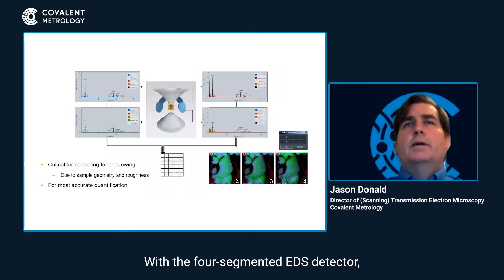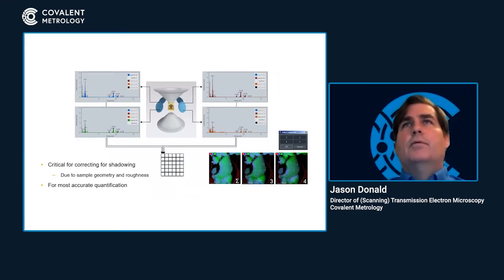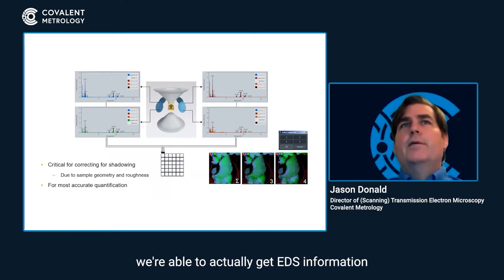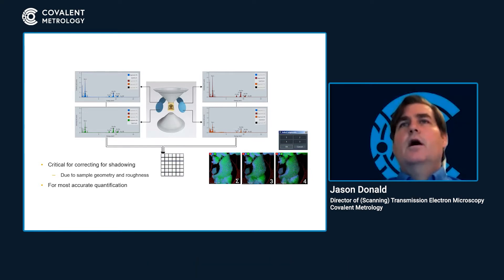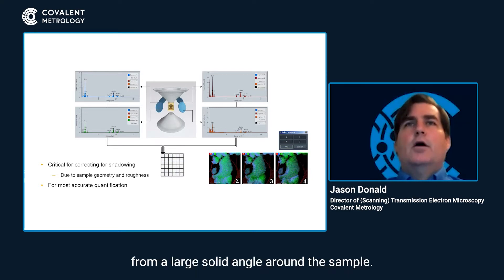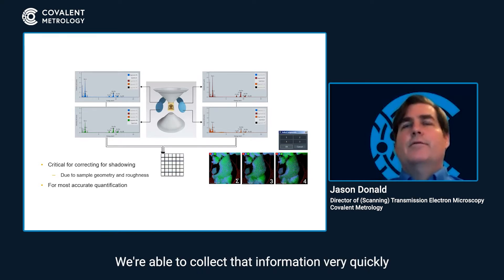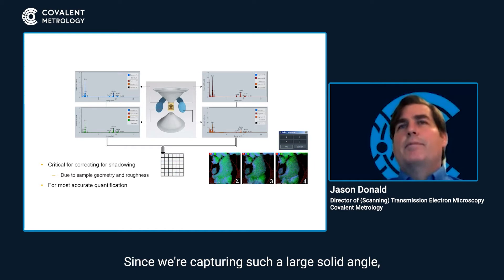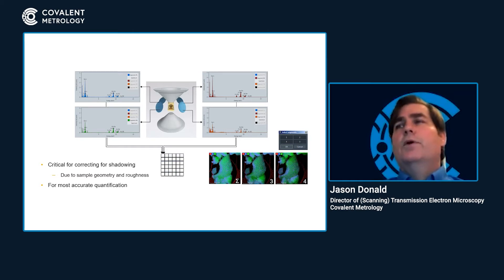With the four-segmented EDS detector developed by Thermo Fisher, we're able to actually get EDS information from a large solid angle around the sample. We're able to collect that information very quickly with the high brightness source.